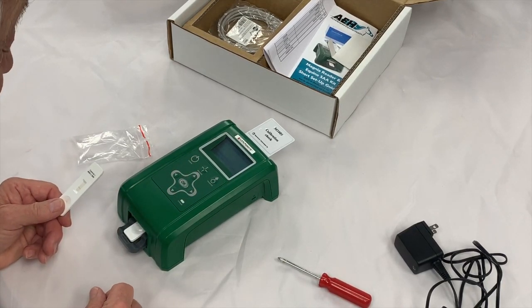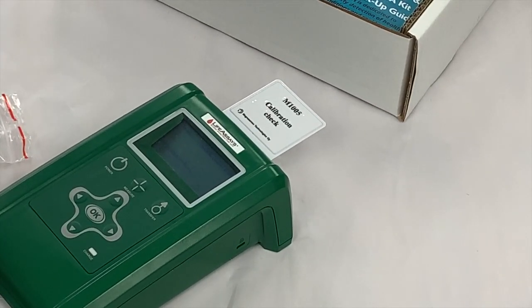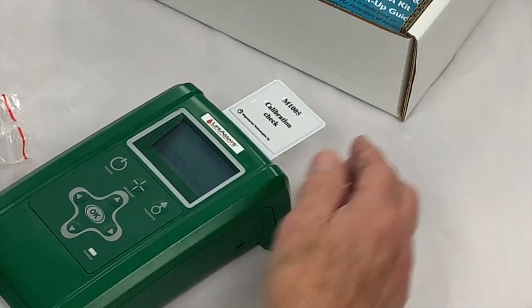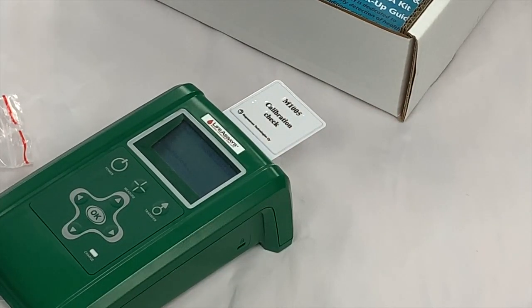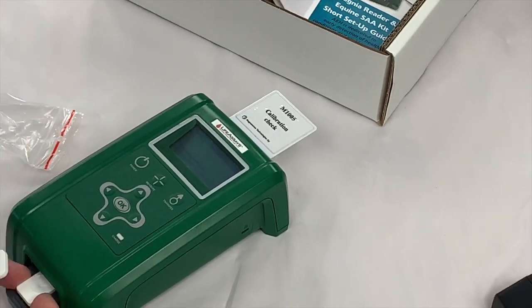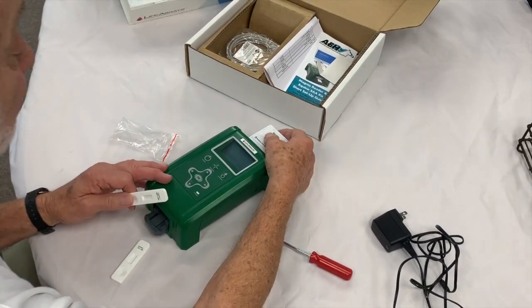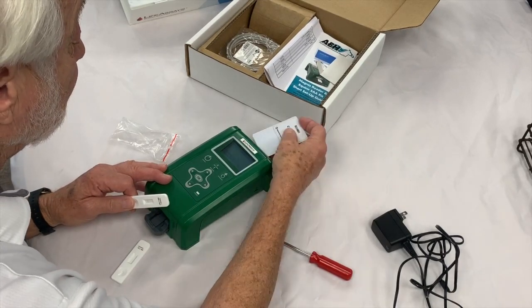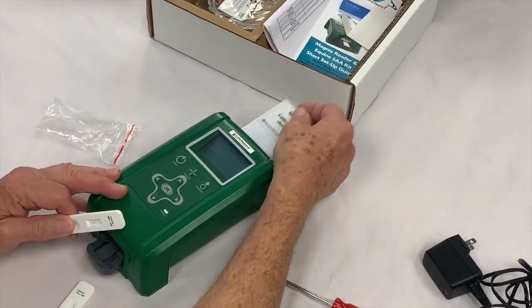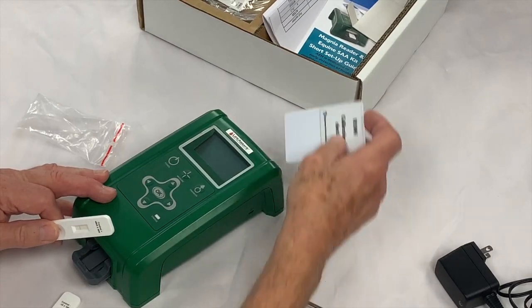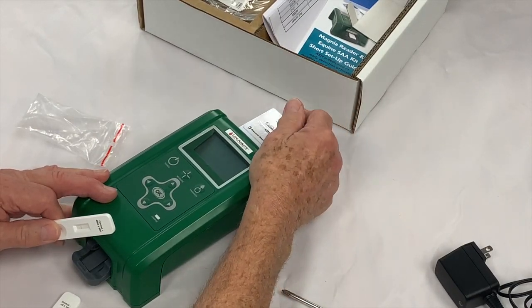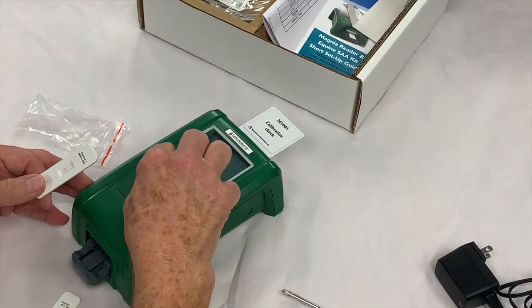Number 5, after the results are ready, record them. Number 6, compare the results with the allowed values printed on the calibration cartridge. Number 7, repeat the steps from 3 to 6 using the second calibration sample card. If the results do not match with the allowed values, clean the sensor head. Once clean, repeat manual calibration check from the beginning.